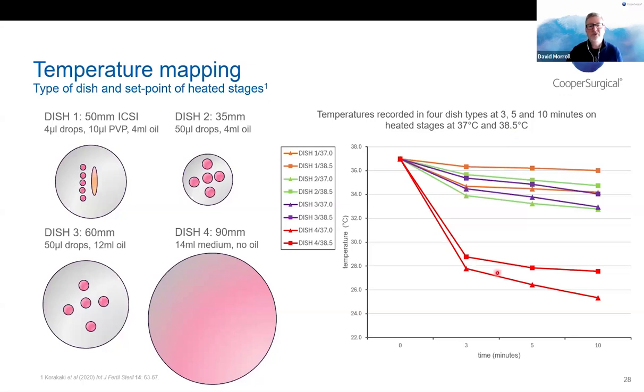And again, what you can see is if you have a look at the lines in the same color, they will all decrease over time. So at 3 minutes, they'll drop, and they'll drop from the starting temperature at 37 degrees. And what it shows here again is that if you have a higher starting temperature on your heated stage, it is more protective. But it's also important to note that you have to do the temperature mapping to make sure that higher starting temperature isn't going to cook the gametes and embryos that you put on them. So they are likely to cool down.